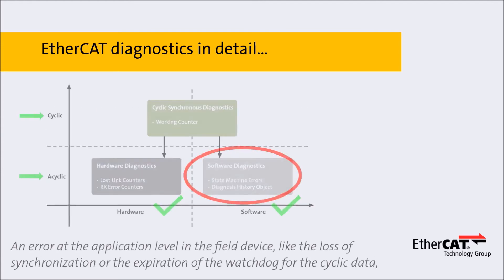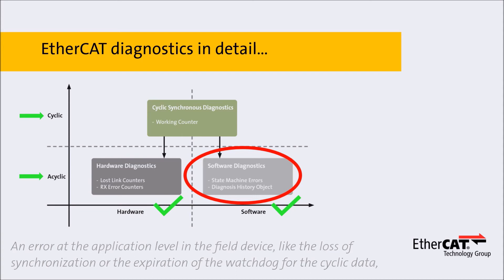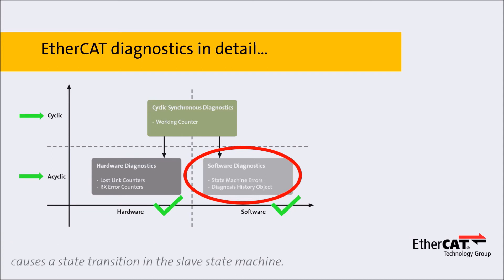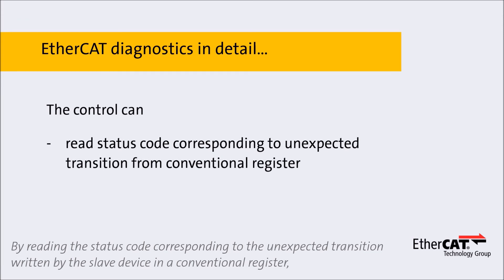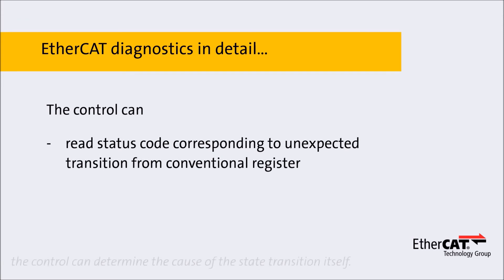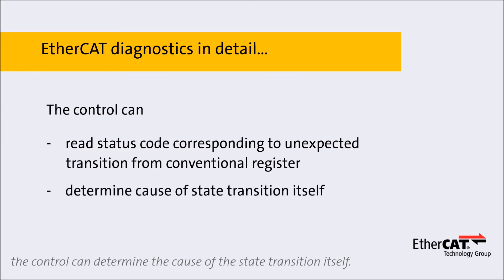An error at the application level in the field device, like the loss of synchronization or the expiration of the watchdog for the cyclic data, causes a state transition in the slave state machine. By reading the status code corresponding to the unexpected transition written by the slave device in a conventional register, the control can determine the cause of the state transition itself.